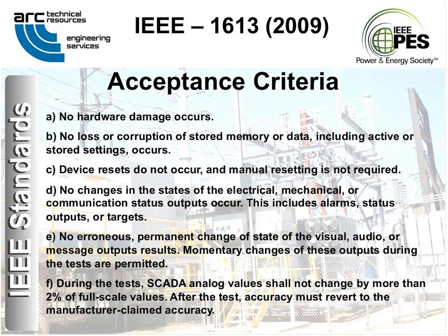That acceptance criteria we've been dancing around about, it's here. 61850-3, our European model, borrowed, word for word, the IEEE 1613-2009 acceptance criteria, which is shown here. So did we. Since 1613.1 is an extension of 1613, every word in 1613 applies in 1613.1. So at least on both sides of the ocean now, we are using exactly the same acceptance criteria. They borrowed ours and we agreed to allow them to use it.